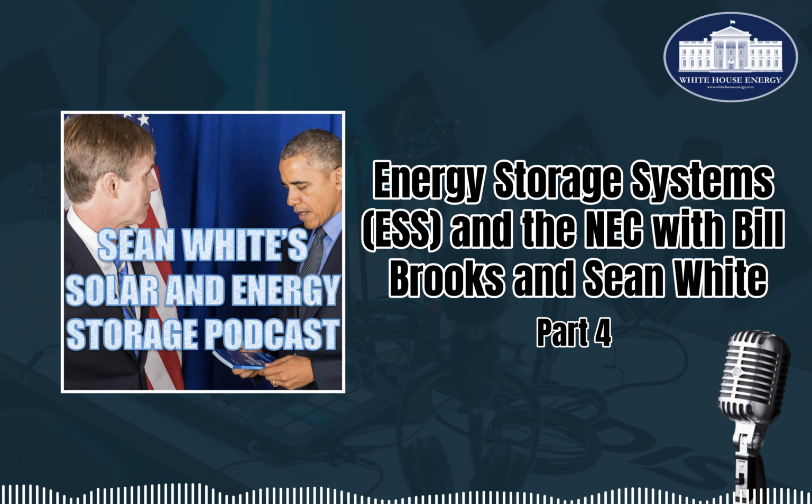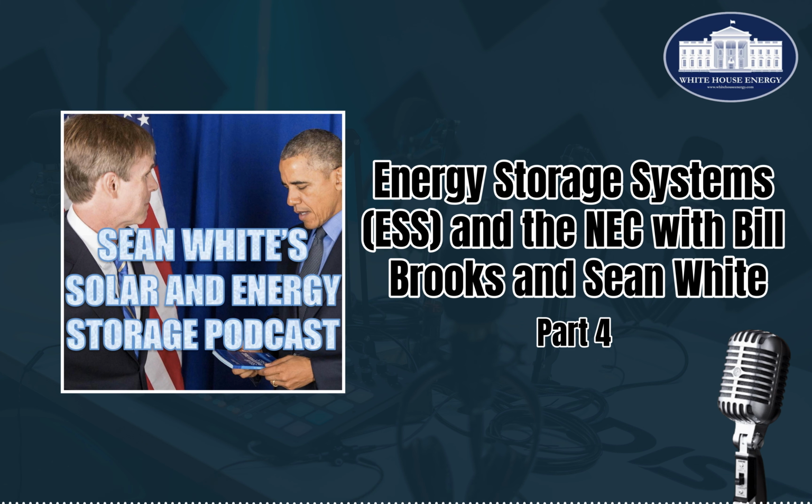And so what we did is we said, okay, we'll use the tap rule and we'll pretend like the PV system has the same fault current characteristics and capabilities as the utility. Now, does it? Of course not. We generalized Article 705 to all power sources, so you could have a power source like a synchronous generator or something like that, even though they're rare, that could be feeding current and fault current into that feeder. And then these tap rules would be preserved because they're still very conservative even for a generator.